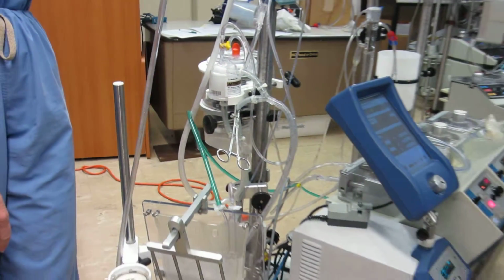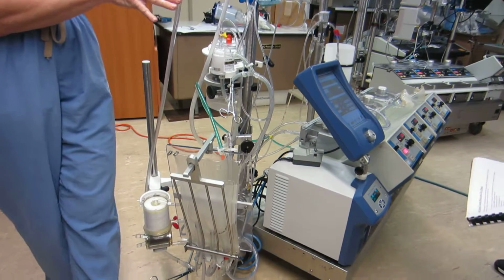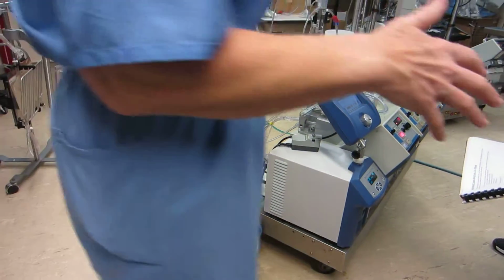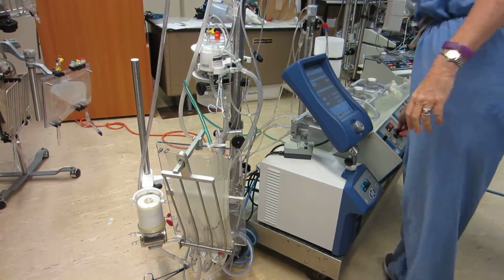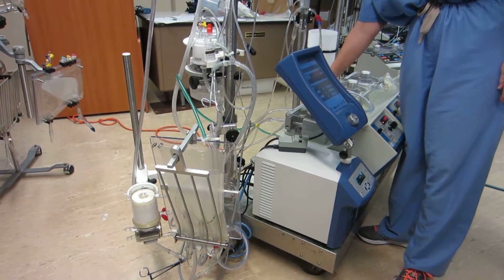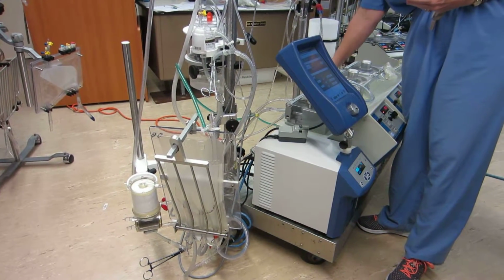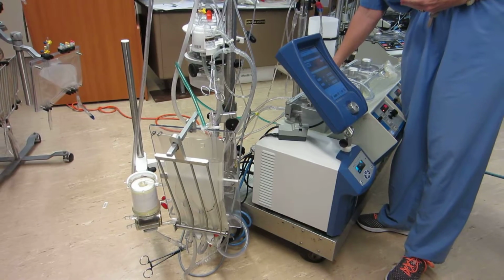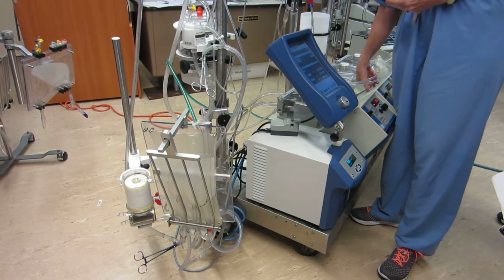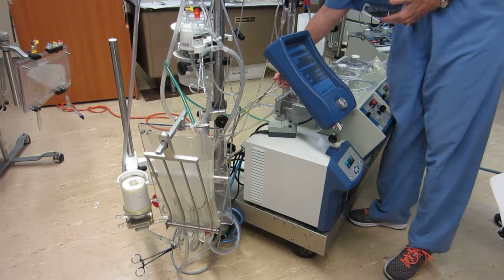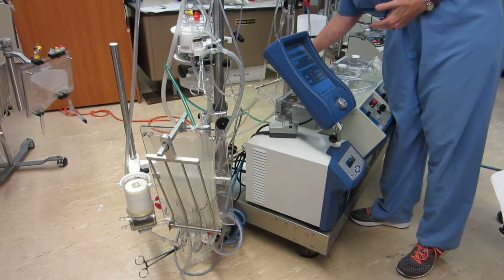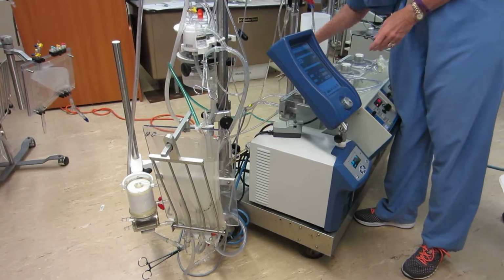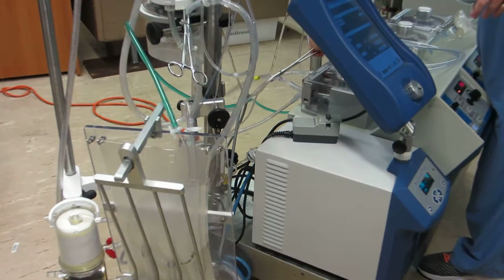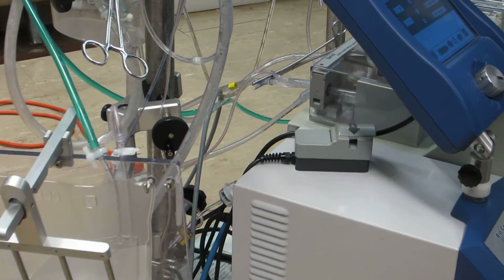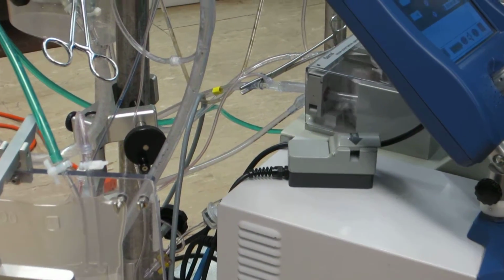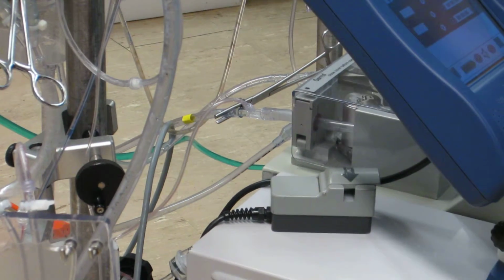Okay? You're going to put your suction and vent in place. You must at the least have your suction in place and set your occlusion on your suction, because you're going to use that to evacuate the excess CO2 out of the circuit. So at least you have to have an occlusion on your suction. You'll notice I picked a suction line that has that luer lock connector. And all these days you probably were wondering why we had that luer lock connector on some of our suctions and not on others. Now you know why.